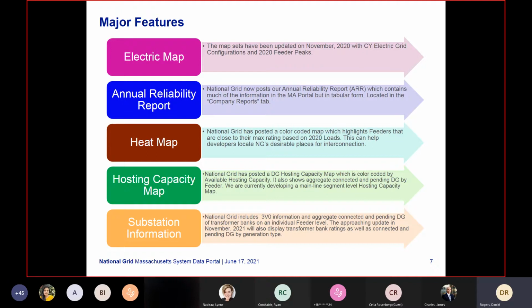The future of the hosting capacity map is going to a segment level mainline hosting capacity. So for the length of the lines, we would calculate the variable level of hosting capacity based on different mainline fuses, reclosers, supervisory controls, things along that line.